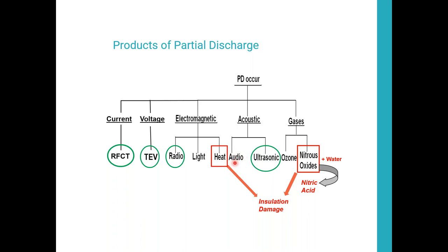Okay. You may be able to actually hear it with your ears. I was at a paper mill where just standing next to a section of switchgear, you could hear the buzzing of the discharge from the outside with the doors closed. That's going to be very advanced if you could hear it. It's a surface discharge typically, very advanced. Hopefully with our testing and test procedures that are going to be developed over time, we're going to be able to address it well before it gets to that point, and actually be able to do easy repairs as opposed to having to do replacements for it failing on us.